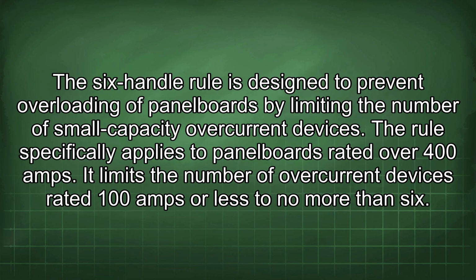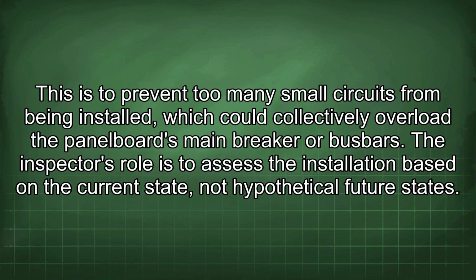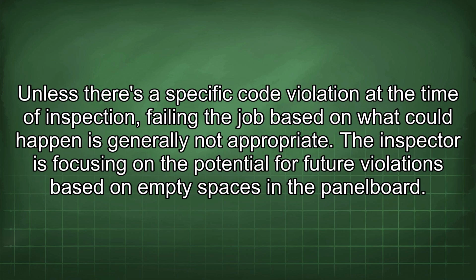The six-handle rule is designed to prevent overloading of panel boards by limiting the number of small-capacity overcurrent devices. The rule specifically applies to panel boards rated over 400 amps. It limits the number of overcurrent devices rated 100 amps or less to no more than 6. This is to prevent too many small circuits from being installed, which could collectively overload the panel board's main breaker or busbars. The inspector's role is to assess the installation based on the current state, not hypothetical future states. Unless there is a specific code violation at the time of inspection, failing the job based on what could happen is generally not appropriate.